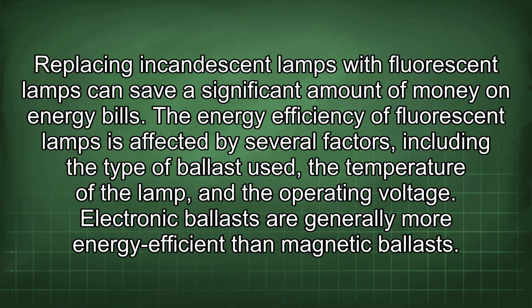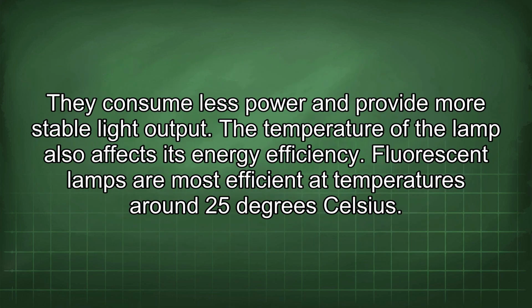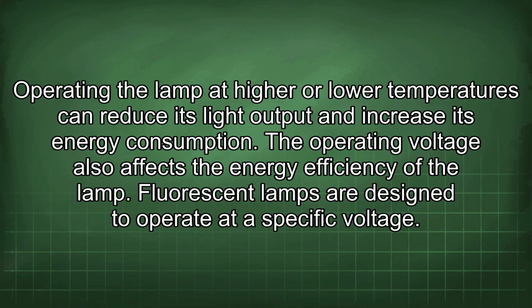Electronic ballasts are generally more energy efficient than magnetic ballasts. They consume less power and provide more stable light output. The temperature of the lamp also affects its energy efficiency. Fluorescent lamps are most efficient at temperatures around 25 degrees Celsius. Operating the lamp at higher or lower temperatures can reduce its light output and increase its energy consumption.